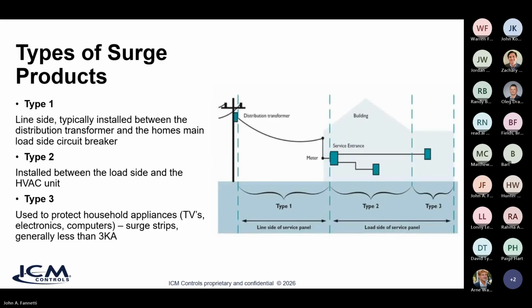So what types of surge can you get? You can get a type 1 surge, which is a line side surge. So that's happening really at the power pole itself, more at the transformer, and it's hitting the mains coming in. Then you have a type 2 surge that can be beyond the breaker, all right, and that can happen on the load side of the service panel.